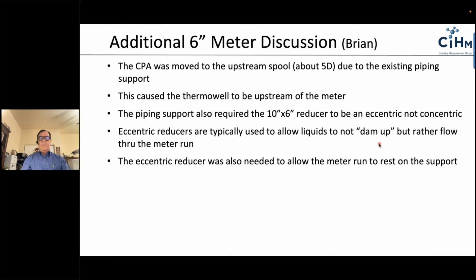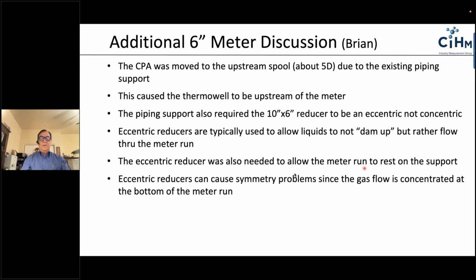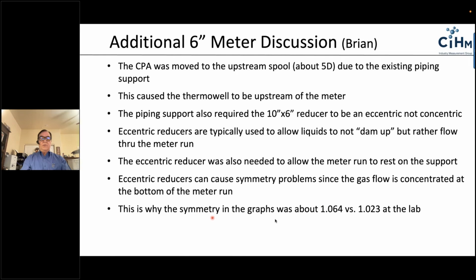Yeah, and again, a lot of times these eccentric reducers are used to allow the liquids to flow through the meter, but in this case, it was used primarily to allow the meter to rest on the supports. So these eccentric reducers can cause distortion in the profile because you're allowing all the gas velocity to enter at the very bottom of the CPA flow conditioner, but the CPA 55E did an excellent job of getting the profile back to somewhat normal, even without any settling zone upstream of the flow conditioner. This is why the symmetry went from about a 1.023 up to about a 1.064.